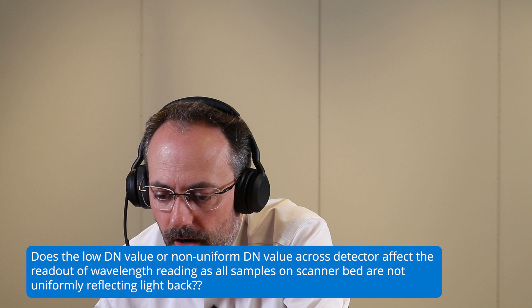Does the low DN value, digital number value, or non-uniform digital number value across the detector affect the readout of wavelength reading, as all samples on the scanner bed are not uniformly reflecting light back? Here you are speaking about spatial non-uniformity, and actually you could see this on our scanner, because we have 2 bars of 3 halogen bulbs, so you have a brighter spot, a darker one, brighter, darker, and so on. This non-uniformity, spatially speaking, is corrected when you normalize the data. Basically you take the white reference, the dark reference, and then you normalize with respect to those. And then you do it line by line. Remember, we are using a hyperspectral camera, which is a line scan device, so you can process or normalize the data for each pixel along the line. Then you correct this type of non-uniformity.